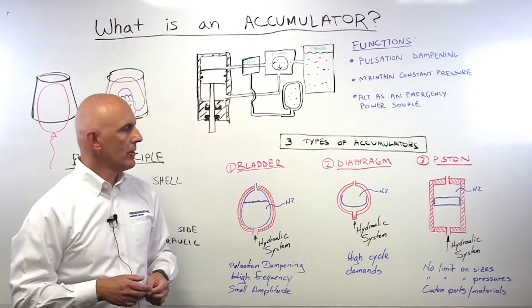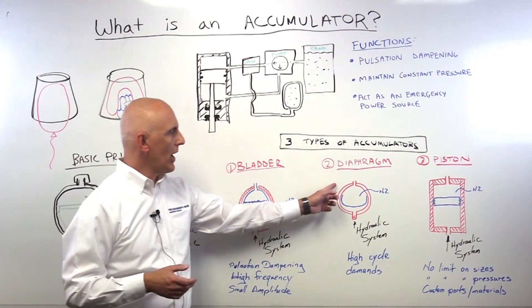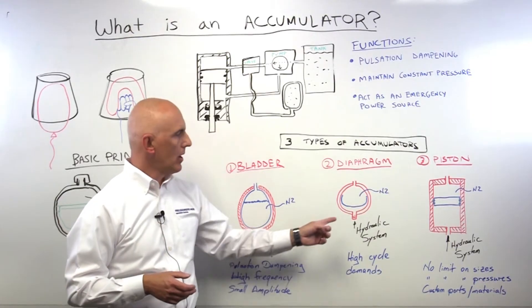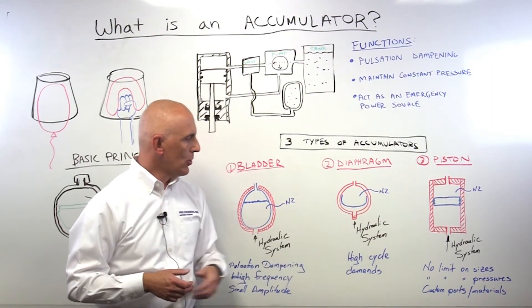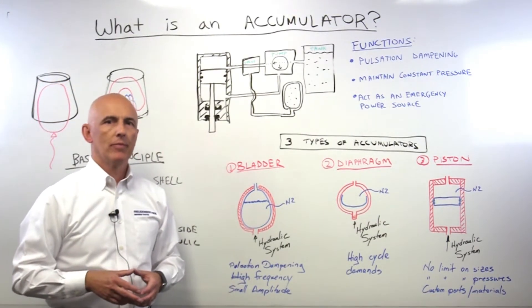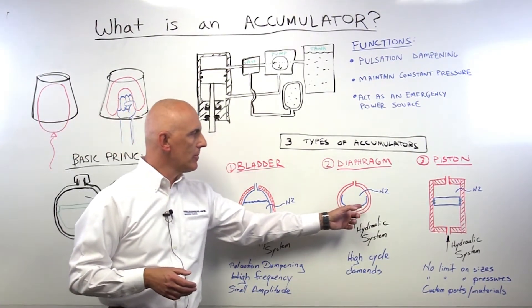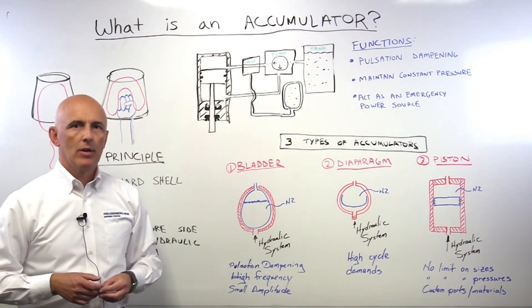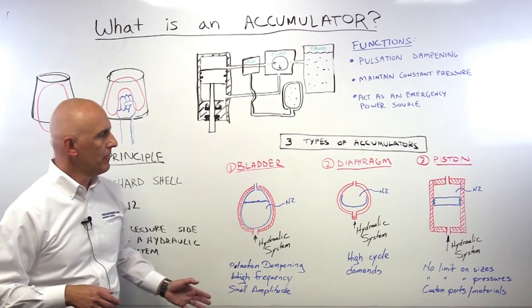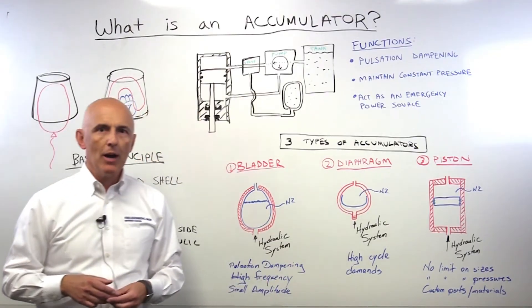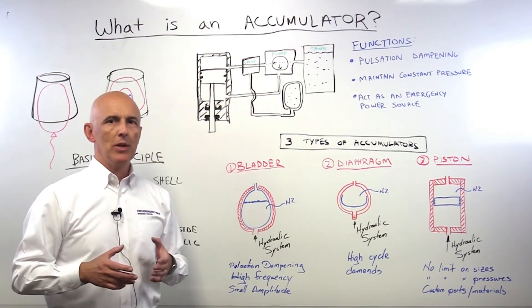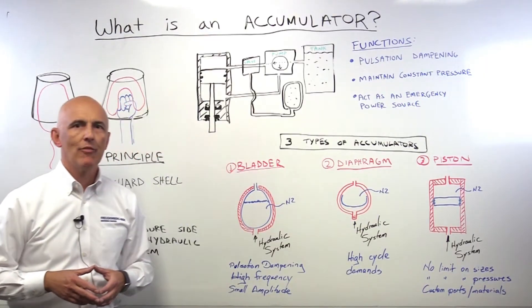Then we go to the diaphragm type accumulator. Basically the same — you have a carbon steel shell, but instead of a bladder, you have a diaphragm. Also a pre-charge of nitrogen, and this portion is connected to the system. Very similar application to the bladder type accumulator, but with an advantage: since you don't have a seam in the diaphragm, you don't have the restrictions of the bladder type. The application is pretty much the same, but this is a really reliable accumulator especially when you have high cycle demands — 1 million, 2 million, 3 million cycles. This is where to use a diaphragm accumulator.